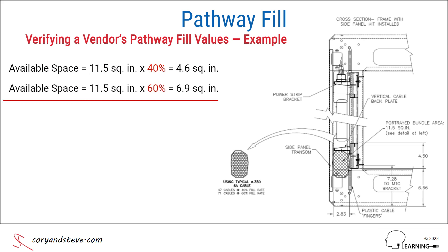So, we have either 4.6 square inches for the cables with 40% maximum fill, or 6.9 square inches with 60% maximum fill.